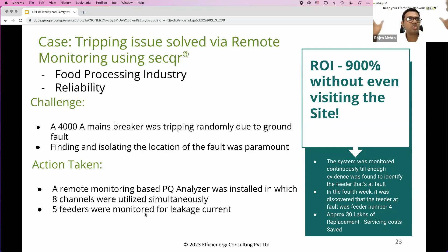We monitored 5 feeders for leakage current. Okay, because ground fault was one of the culprits, but where was it coming from? Whether it was there or not, whether it was a spurious breaker, or because they were thinking of replacing the breaker, right? It's a very costly affair. A 4,000 ampere breaker is not less than 20, something in the range of 5 to 7 lakhs, and with the associated installation costs and so on. So all of this was saved by installing this at multiple channels.